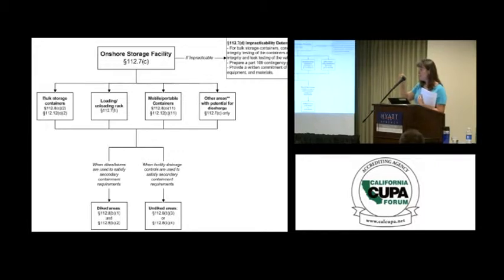So take a close look at those SPCC qualified facility templates and the boxes that they check. Sometimes they're just all left blank. I had a pretty big chain of oil change facilities that left a whole bunch of those boxes blank on their template because they thought this was for oil rigs. For some reason they saw the word shore and they think that's something like on a port or something like that. So just to let you know.